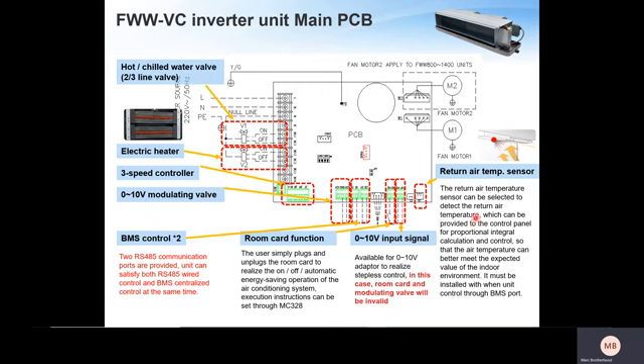And we have a return air sensor. Can be selected to detect your return air, which then will obviously through proportional integral calculation, the unit will make judgments so that the air temperature can be better met to expect the desired set points. It also has to be installed if you want to use BMS options.